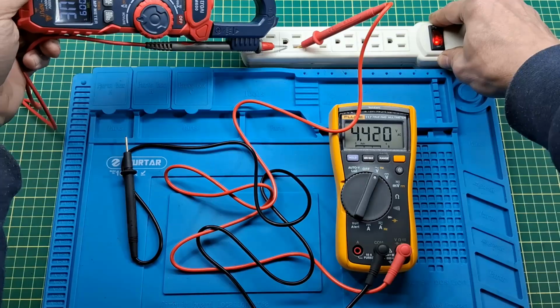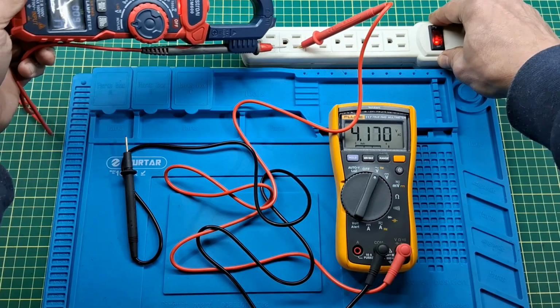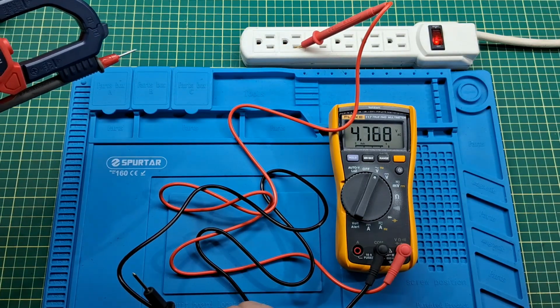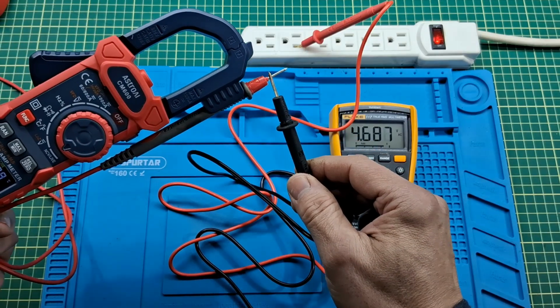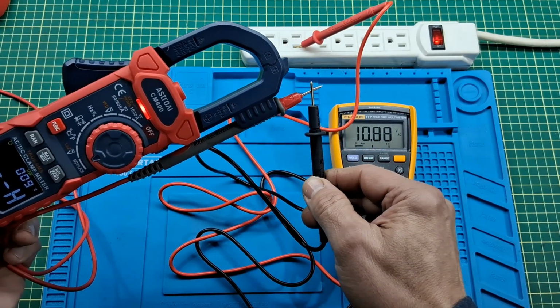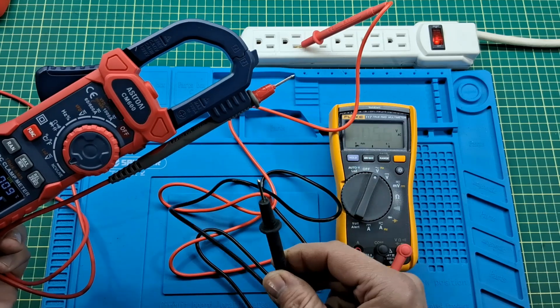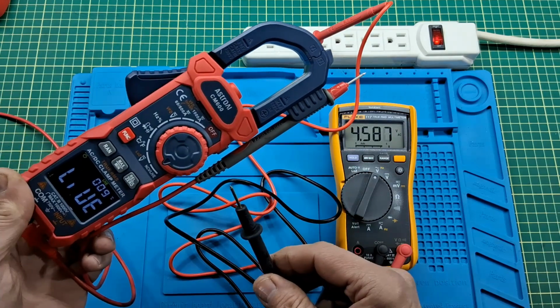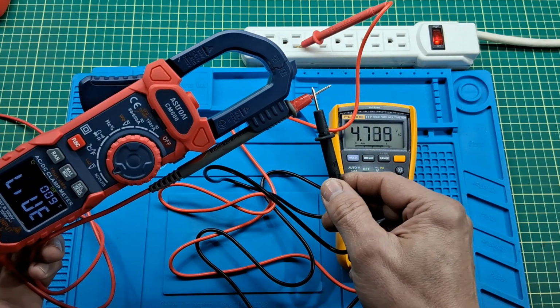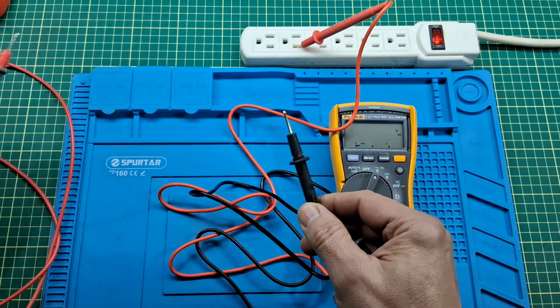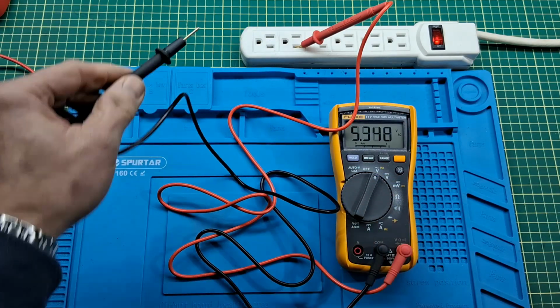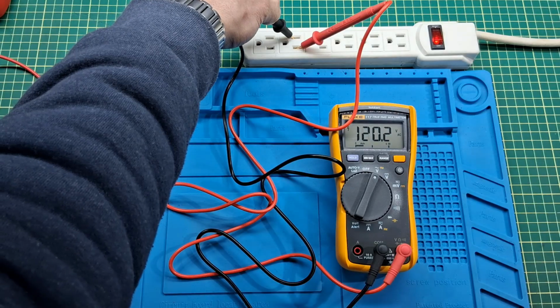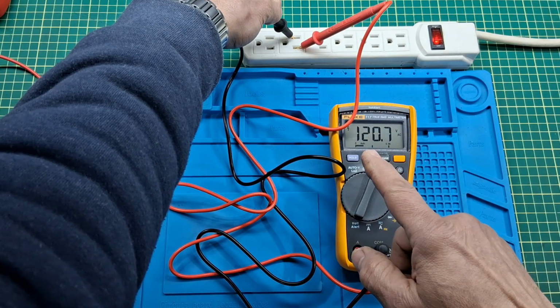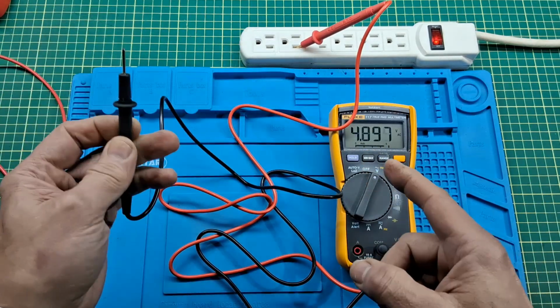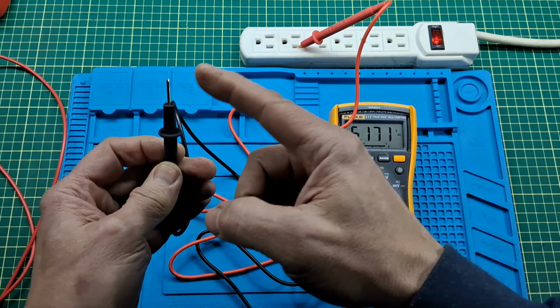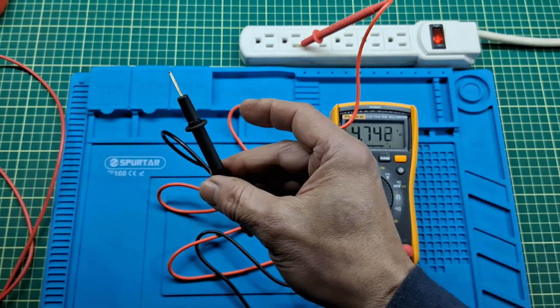Neutral: silence. The red probe: live voltage. Danger. Now the black probe: sure enough, it is energized. Once again, we read 120 volts. No fooling around, so we can assume it would be dangerous to touch.